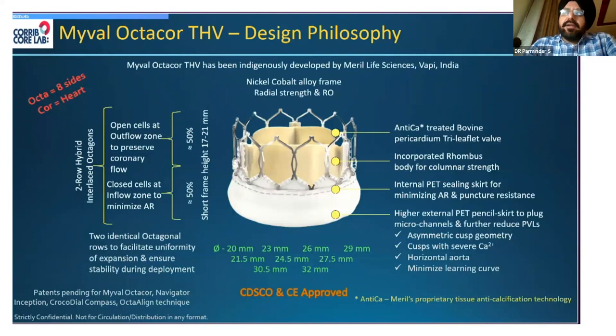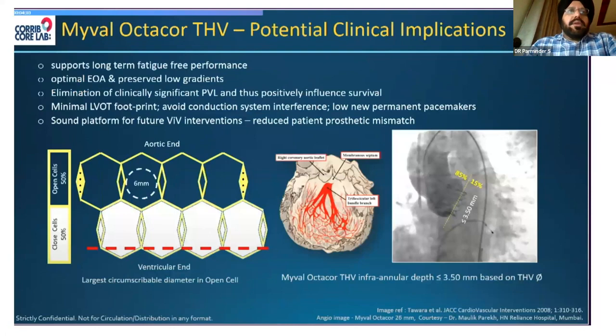And there is an additional PET skirt to plug the PVLs. So this valve is an improvement over the existing Myval and provides better opportunities for future coronary access. This Octacor valve supports fatigue-free performance. It has an optimal effective orifice area and provides low gradients and significant elimination of clinically significant PVL, and thus positively influences survival. And because it is deployed 3.5 millimeters or less in depth into the LVOT below the annulus, the chances of having conduction disturbances are very low, which is otherwise also low with the balloon expandable valves. And it provides at least a 6 millimeter access to the coronaries, which is quite larger in comparison to our Edwards valve.